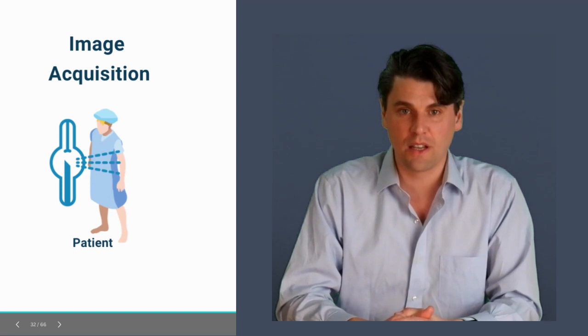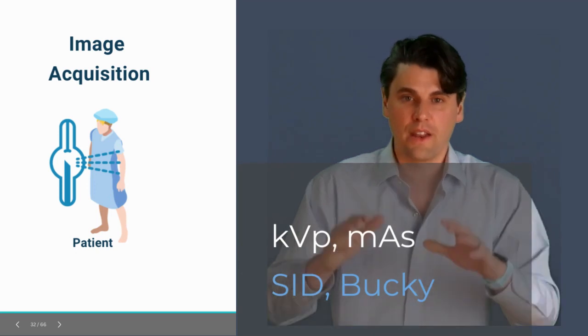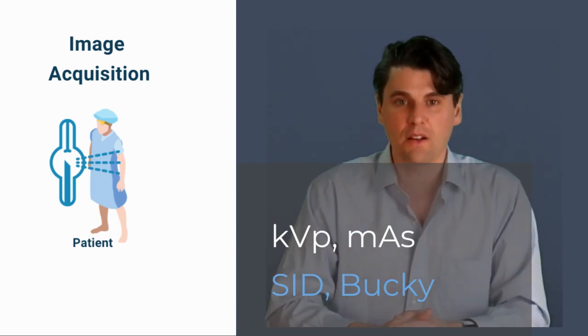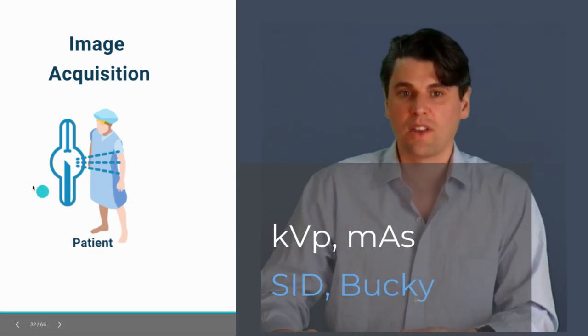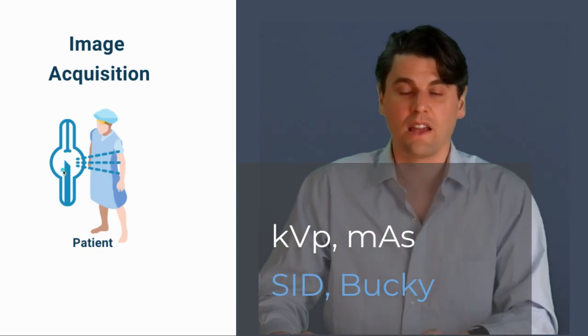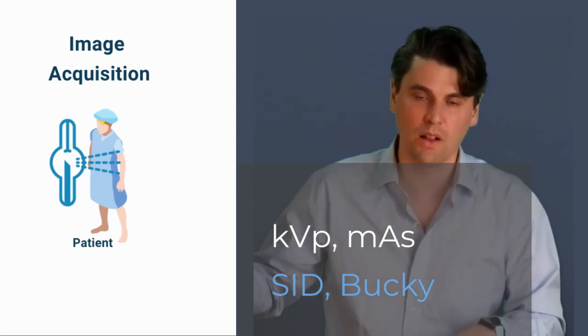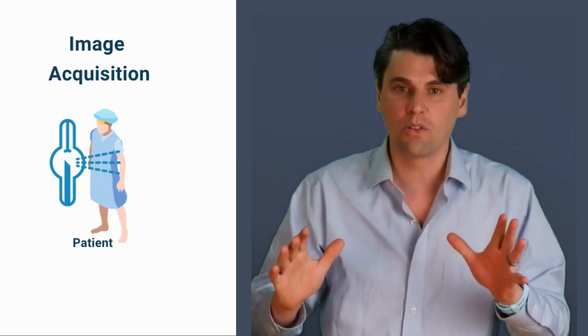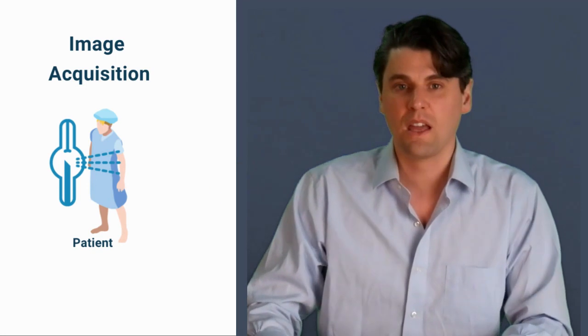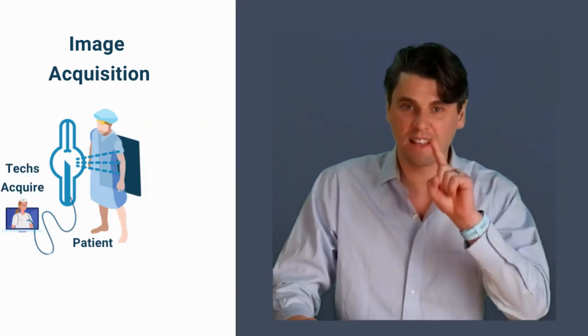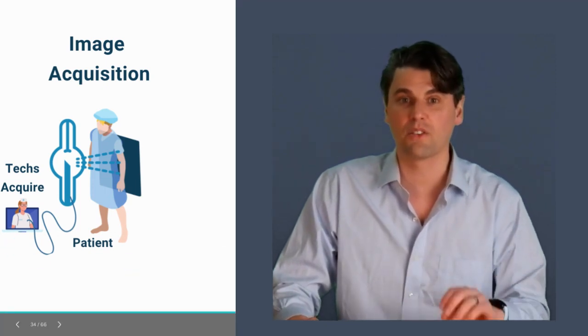Starting first with the image acquisition, you as a technologist are going to be setting the parameters — the technical factors that are most important for your image acquisition. That is exactly the same as with film-based techniques. So you're setting on your x-ray system the KVP, mA, the time, all of these really important factors, as well as your Bucky and your SID. Those are all the same, and the fact that you have a cassette is also the same in computed radiography. You're placing the cassette in there, then performing that acquisition with the technical factors we just talked about.